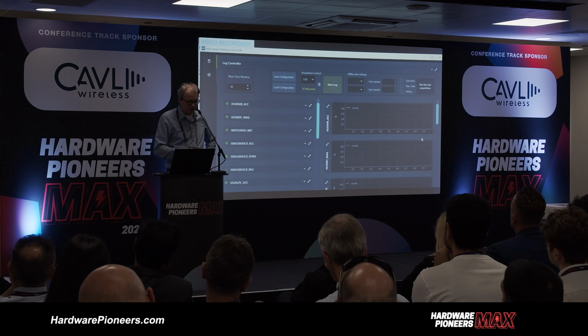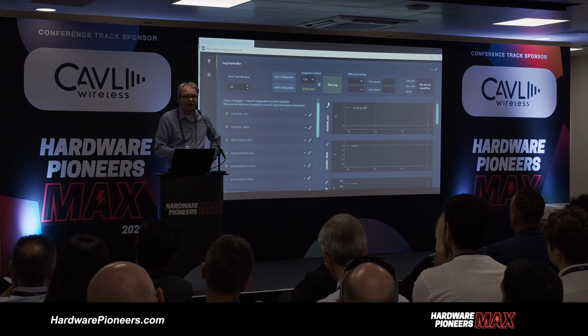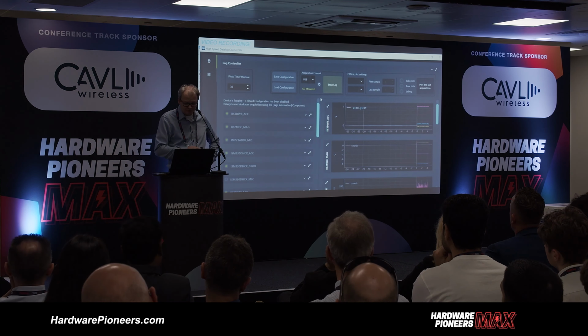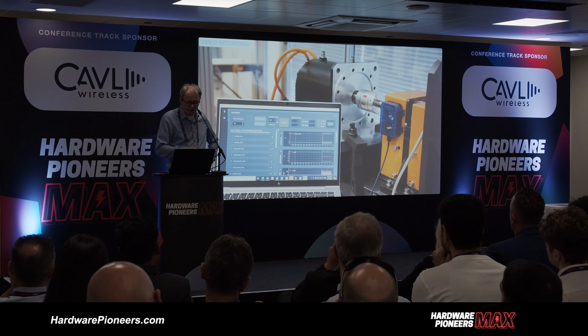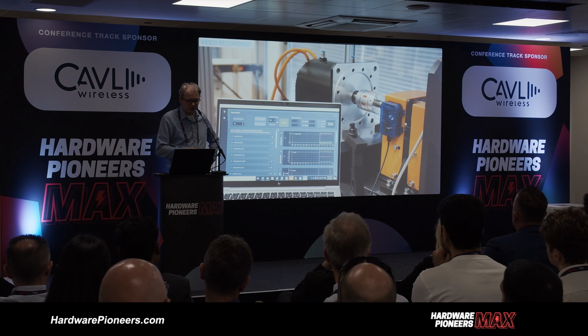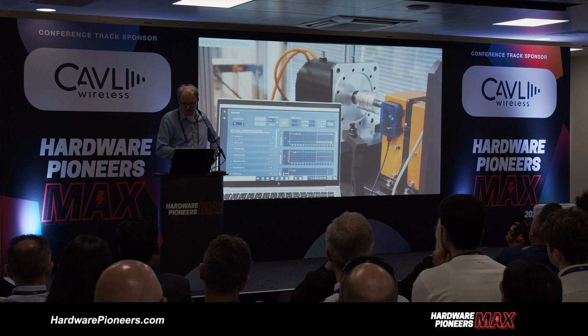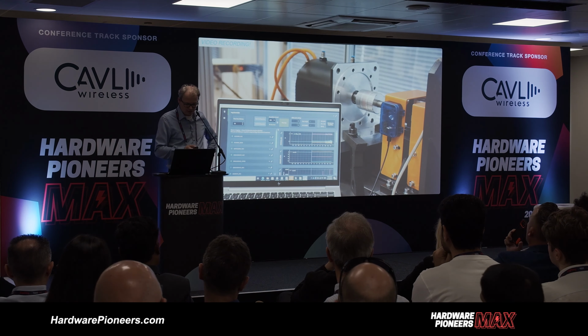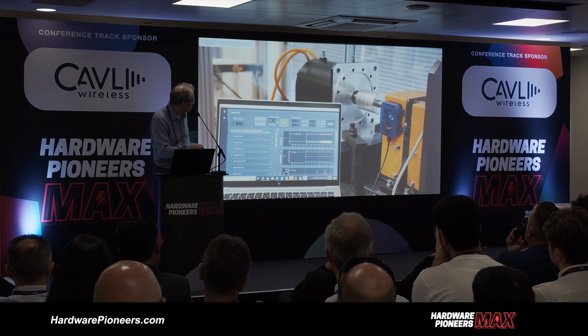And after this, again, we have all the sensors now enabled here. So it's very easy to make data logs from all the sensors. You actually create quite a lot of data using this. And again, we have connected this to the same motor that we have in our motor lab. And yes, you can see in here the vibrations the motor is generating.